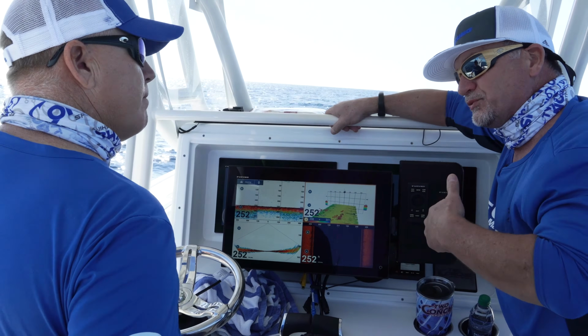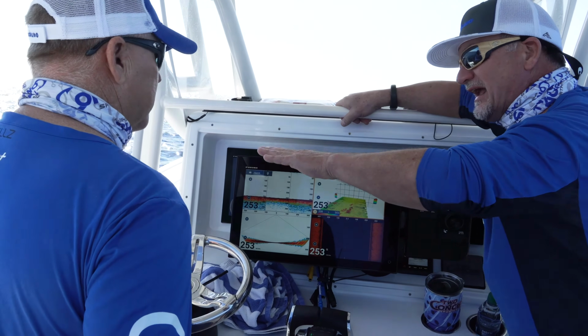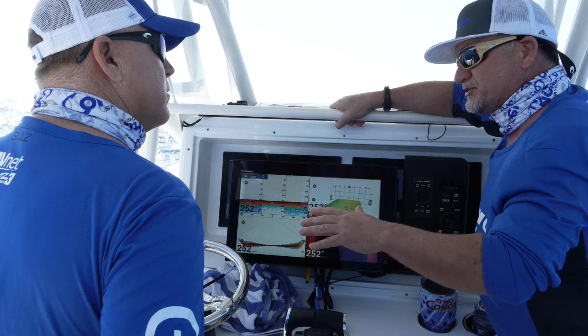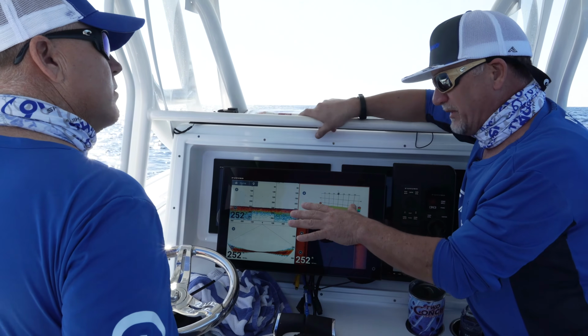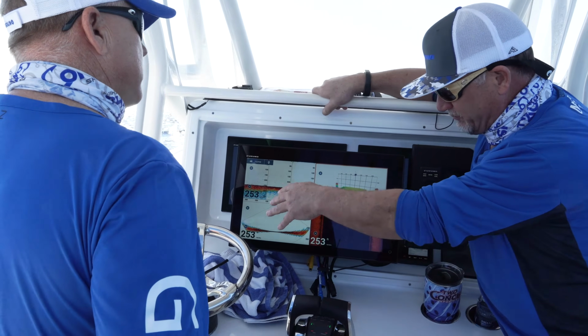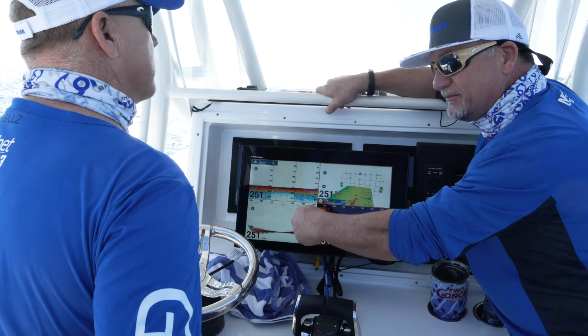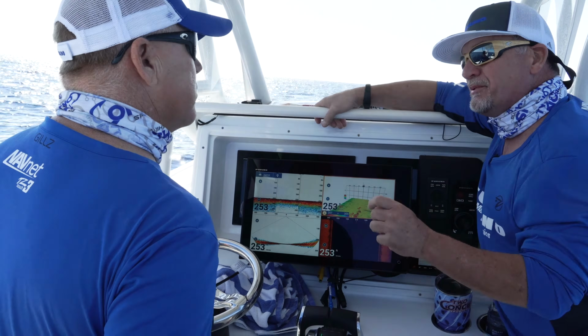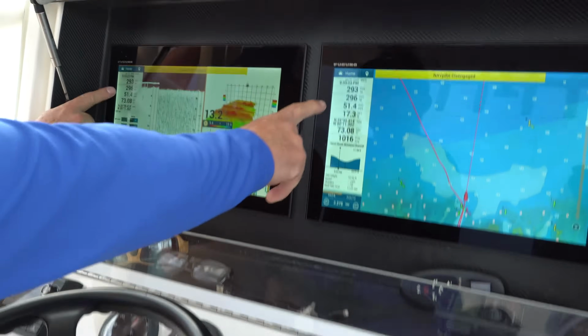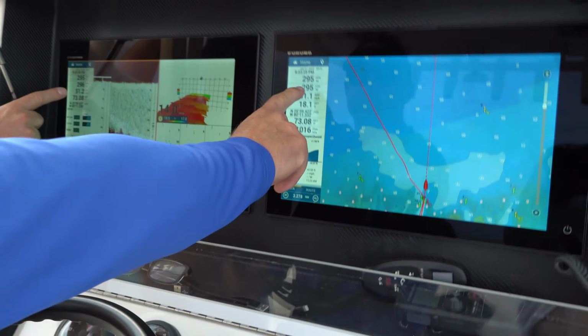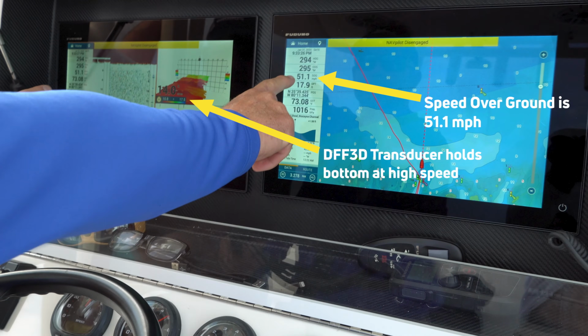While with the DFF3D, we electrically scan 8 elements with a flat bottom transducer. That not only gives you more information in real time and more information directly across the bottom, so we don't have to have this side scan mode, but it works at speed. If you notice with our competitors' products, as soon as you start to go fast, that transducer's got to stick down into the water, it gets turbulence and it washes out. Their systems can't work at speed, the DFF3D can.